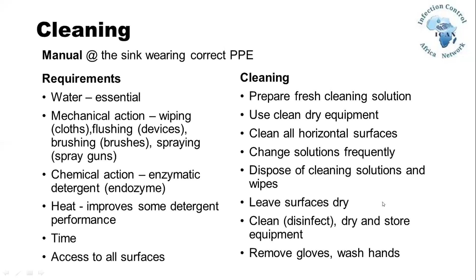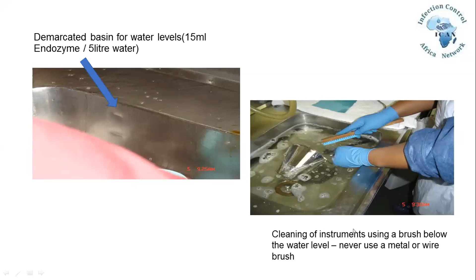Here I've put in some pictures of how we demarcate the basin so that we know exactly what the water level must be for the amount of detergent needed. So here, for 15 mils of Endozime, the enzymatic cleaner, you need to mix it with 5 liters of water. So the staff know that level will be your 5 liter mark, and the higher one would be your 10 liters. Then they'll put 30 mils in. Here's just the cleaning of the instruments using a brush below the water level. Never use a metal or wire brush.